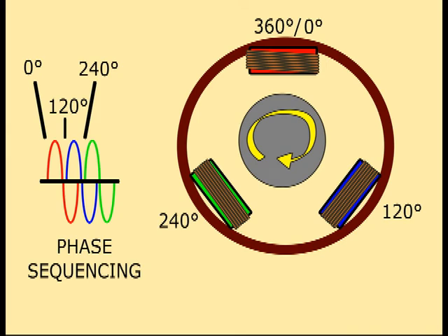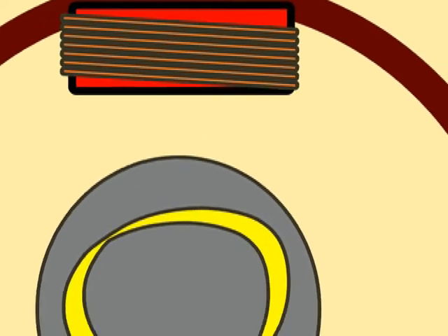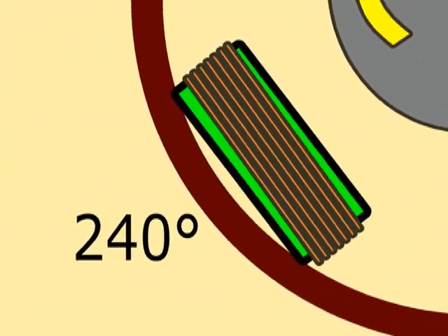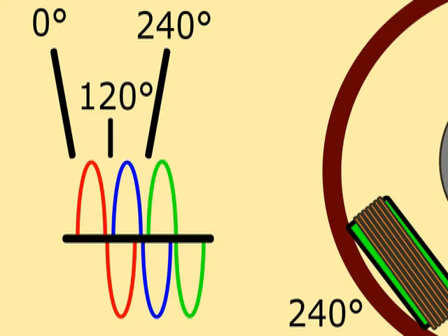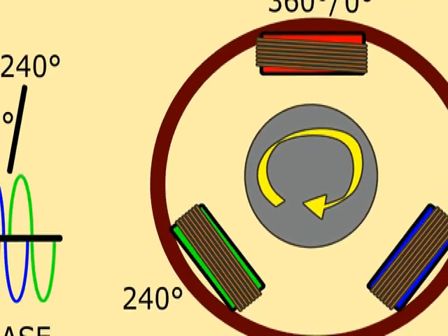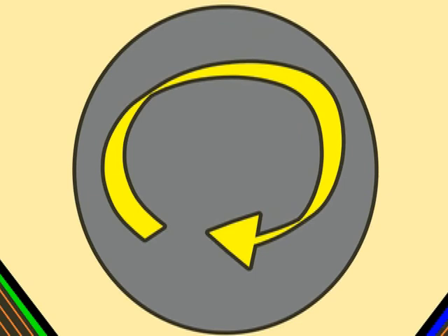Normally, a three-phase industrial electric motor uses a squirrel cage type rotor. The motor has one or more groups of coils distributed 120 degrees apart in its round stator. The three phases arrive from the power company to the motor coils and produce a sequential magnetic field according to the order in which the different phases arrive. This sequential field results in a rotating magnetic field, which induces current in the rotor bar just as it happens in a single phase motor.